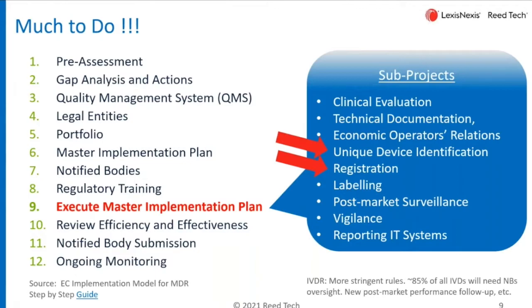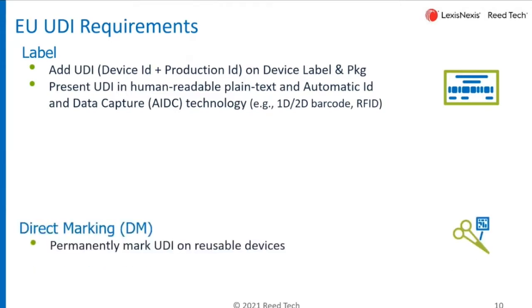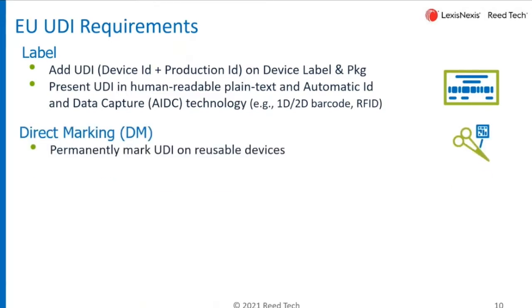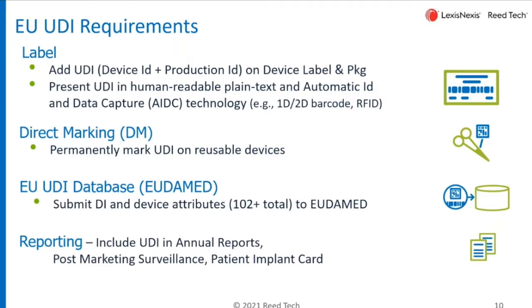Let's take a quick summary of the UDI requirements regarding MDR-compliant devices. There are a couple of major areas. Labeling is obviously a big component — having a unique product identifier on the product and packaging, presenting it human-readable and in a barcode-type format. A subset of all those medical devices qualify as reusable and therefore need to be directly marked. Today our focus is number three: the European Union UDI database, the number of attributes that need to be submitted, and then obviously all the reporting, documentation, procedures, and SOPs that need to be put in place. There are four major tenets of UDI.